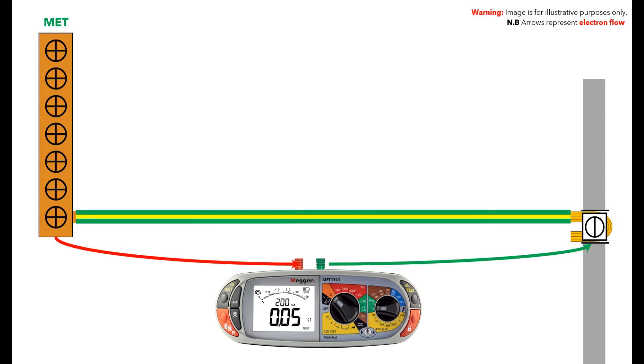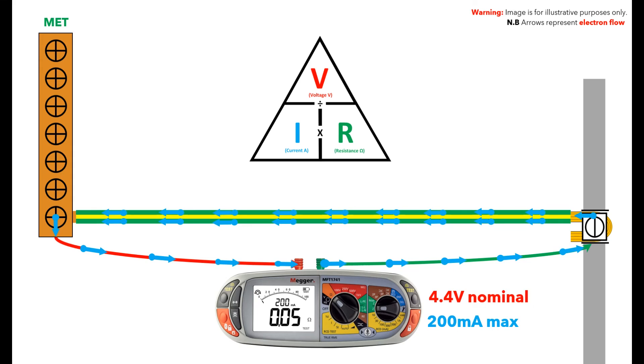If we were to look at this in the simplified model, then we would have the following arrangement. Here you can see the MET connected to the main gas supply by the main bonding conductor. You will know from my video on how the MFT works that the voltage is 4.4 volts nominal and the current limited to 200 milliamps. The electrons flow out of the low ohm resistance tester along the test lead to the bonding clamp, through the main bonding conductor to the MET, and then back into the low ohm resistance tester creating a circuit. But due to the resistance of the circuit, some of the current has been slowed down. The meter can measure and calculate the resistance using Ohm's law. Because the main bonding conductor has a low resistance due to the size of the conductor, electrons can flow more easily, which is why I represented this by using double arrows.